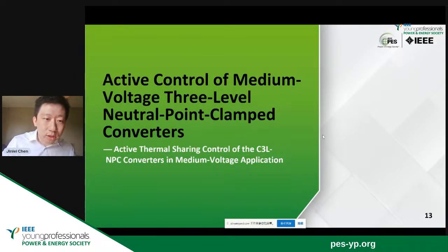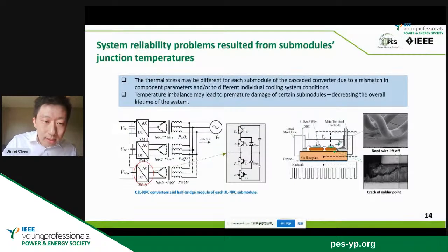Afterwards, to enhance the system reliability, I also developed the active thermal sharing control. First, the system reliability is highly related to the thermal stresses of the power modules. We can see that in each power module, due to the package, the thermal stresses may be high in some modules, and the high overheating of the submodules will cause bond wire lift-off and cracking of solder points, so that some modules may be damaged due to the high thermal stresses, and the reliability of the system will be decreased.